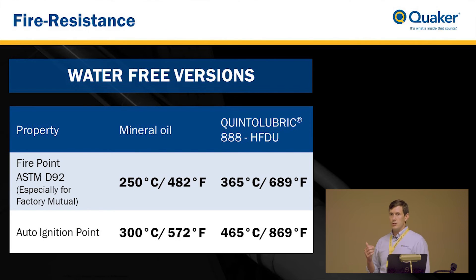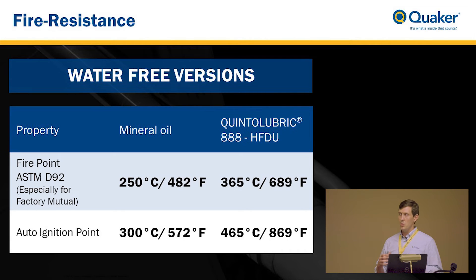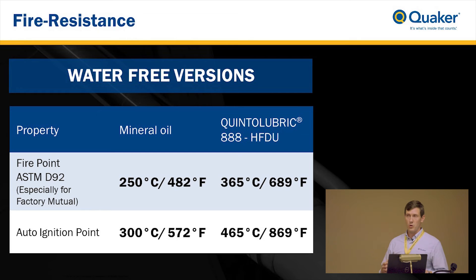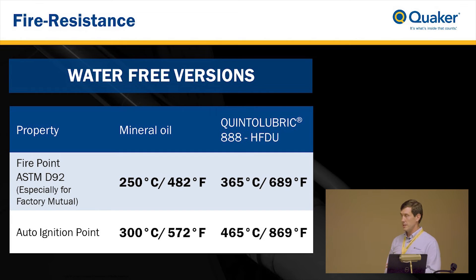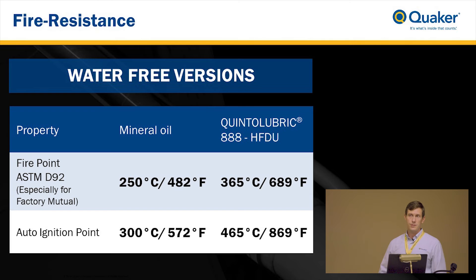Here is a chart showing different temperature thresholds. The fire point is where vapor comes off the fluid and can sustain a flame. The auto-ignition point is where it heats up enough to combust without a flame or spark. The difference between mineral oil and polyol ester is approximately 250°C versus 365°C for fire point, and 300°C versus 465°C for auto-ignition respectively. Phosphate esters add about another 20 to 25 degrees Celsius onto the auto-ignition point.